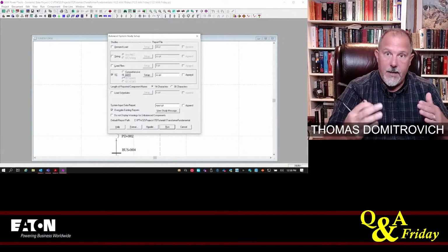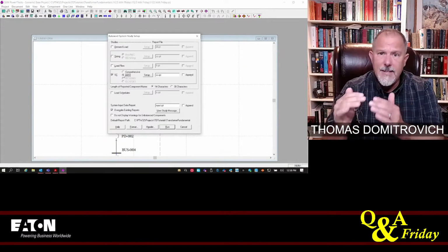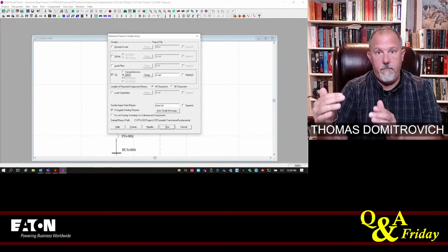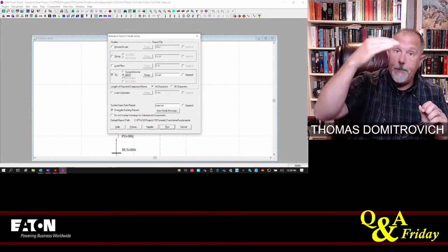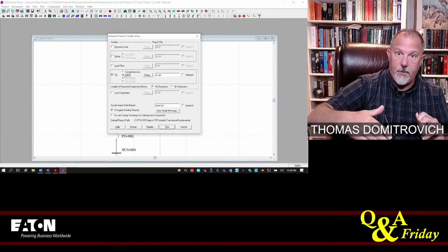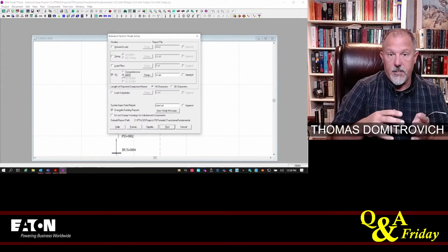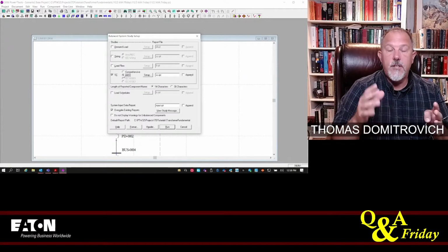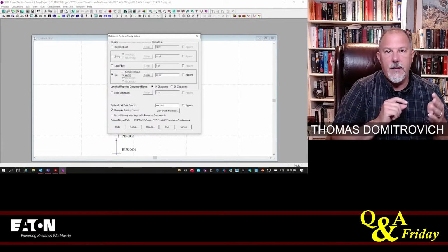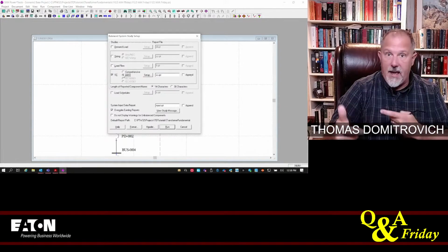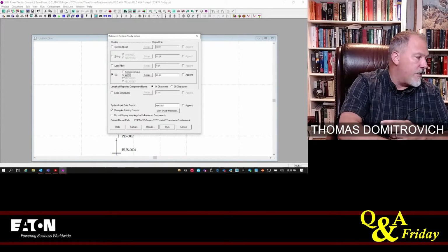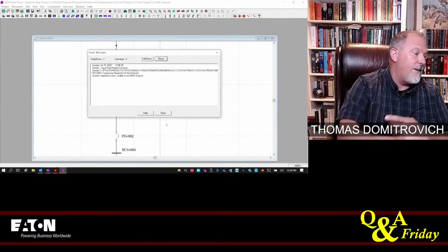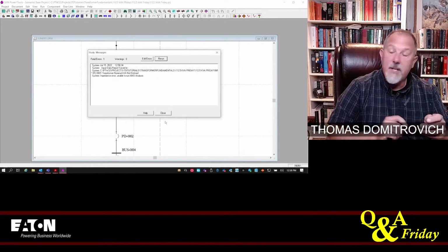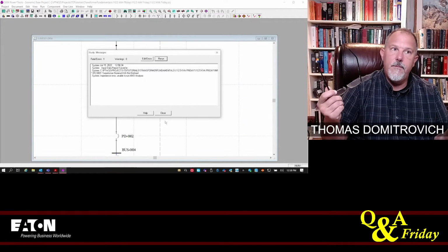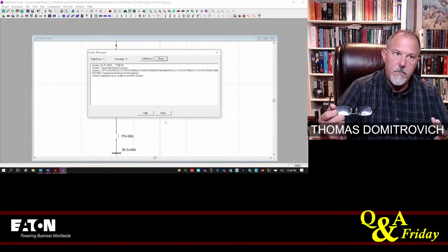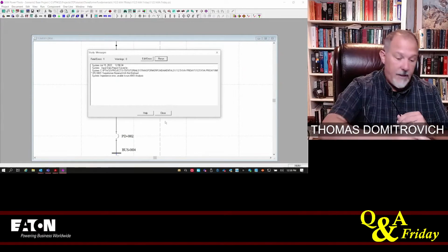The difference there is the ANSI method uses rules of thumb, and it will create an impedance diagram with a real and a reactive component and do your network reduction. So comprehensive will generate a number. It might be a little bit different than ANSI because it does a lot more math in the background. I always just go with the ANSI method because I can select it and actually do it by hand and verify the numbers.